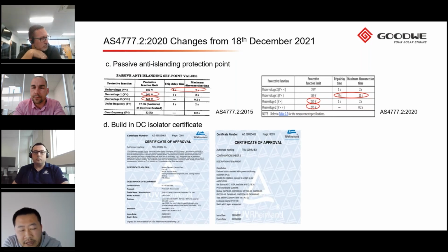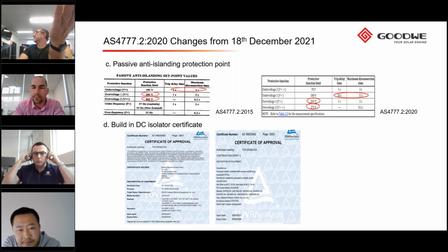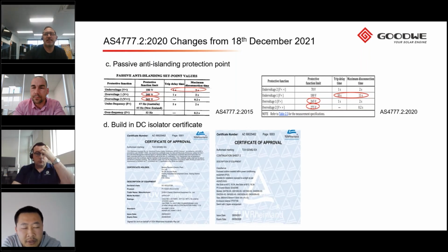Previously, if the inverter manufacturer had a DC isolator, they only needed the general DC isolator certificate from the different testing departments. But right now, besides the DC isolator itself needing to be certified, each inverter needs to certify the DC isolator as well according to the inverter models. So this would be a big change, but from the manufacturer's side, we believe this is a very good movement, which means that by doing this more comprehensive testing, we have more confidence that the DC isolator built into the inverter can better replace the DC isolator either next to the inverter or the DC isolator on the roof as well.